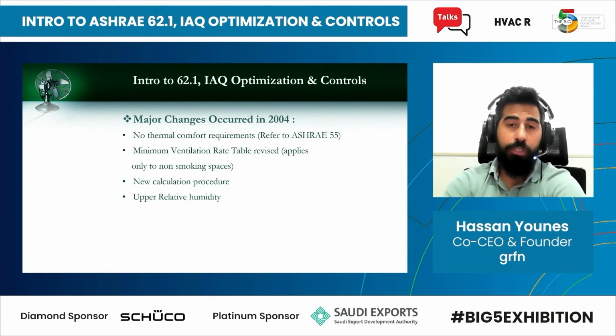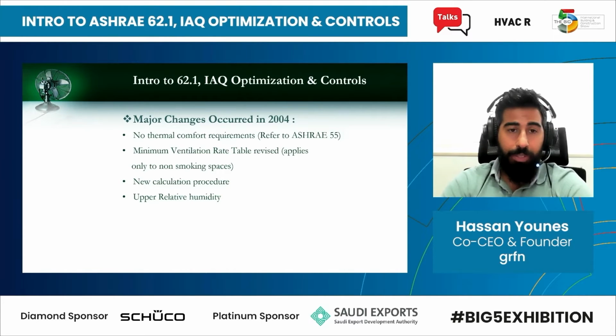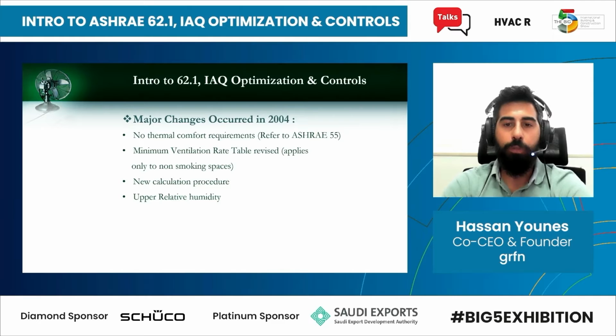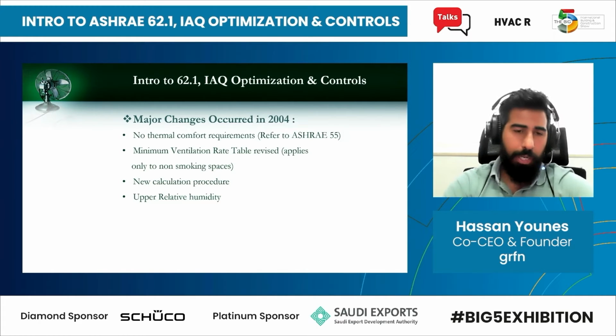Now, what were the major changes in 2004? There were no thermal comfort requirements in the standard. Basically, if you want to look into thermal comfort, you need to refer to ASHRAE standard 55. Minimum ventilation rate tables were revised, and now they apply only to non-smoking spaces. And there was a new calculation procedure that we're going to have a look at. And there was an upper relative humidity limit that was set to 65%, so that no bacteria or, let's say, mold can thrive. We need to keep the relative humidity below 65%.